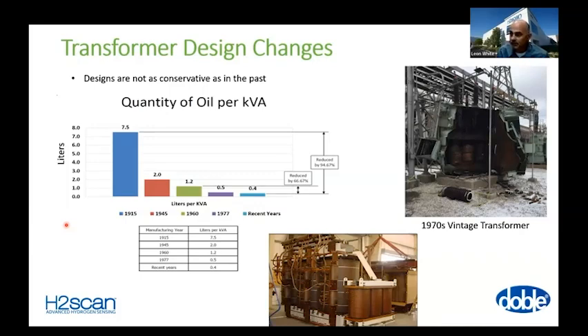But the story behind this transformer was apparently they had some large motors that needed 2 transformers to start up, and 1 transformer was out of service. So they found out the hard way that, yep, you really can't start the big motor with 1 transformer. I had never seen a transformer open up the tank like a door, so I found that to be a very interesting case. And then I'll let Tony talk about the complexities of some of the transformers today on the picture down below.